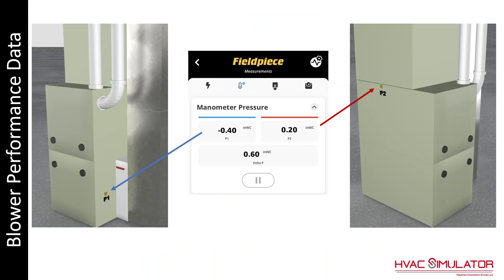P1 is negative pressure in the blower compartment, and P2 is positive pressure below the coil. The recommended place to drill a hole in the furnace is within the top three-quarters of an inch of the furnace, as the heat exchanger is below, so no damage will be done to the heat exchanger.